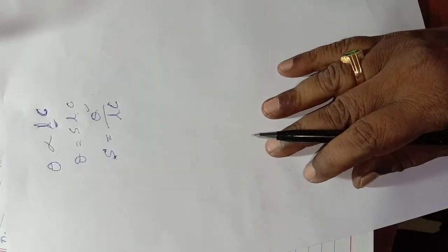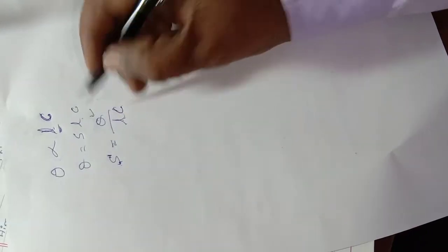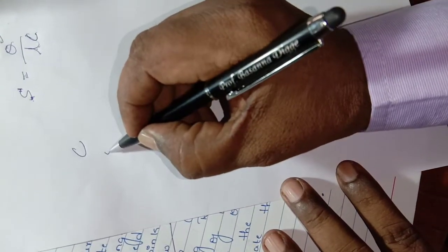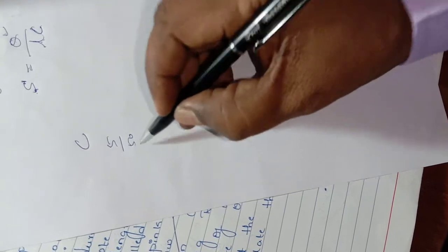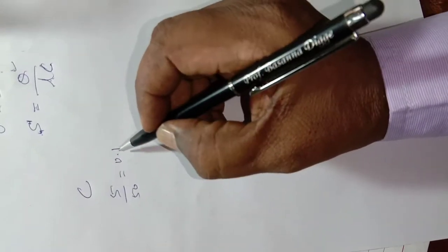The length of the polarimeter tube is fixed and constant, only theta and C values vary, so the specific rotation S can be calculated. So theta can be measured with different concentrations. What are the different concentrations? The first concentration you have to take is 5 gram of sugar dissolved into 50 cc of water. 5 gram dissolved into 50 cc of water gives 0.1 concentration.